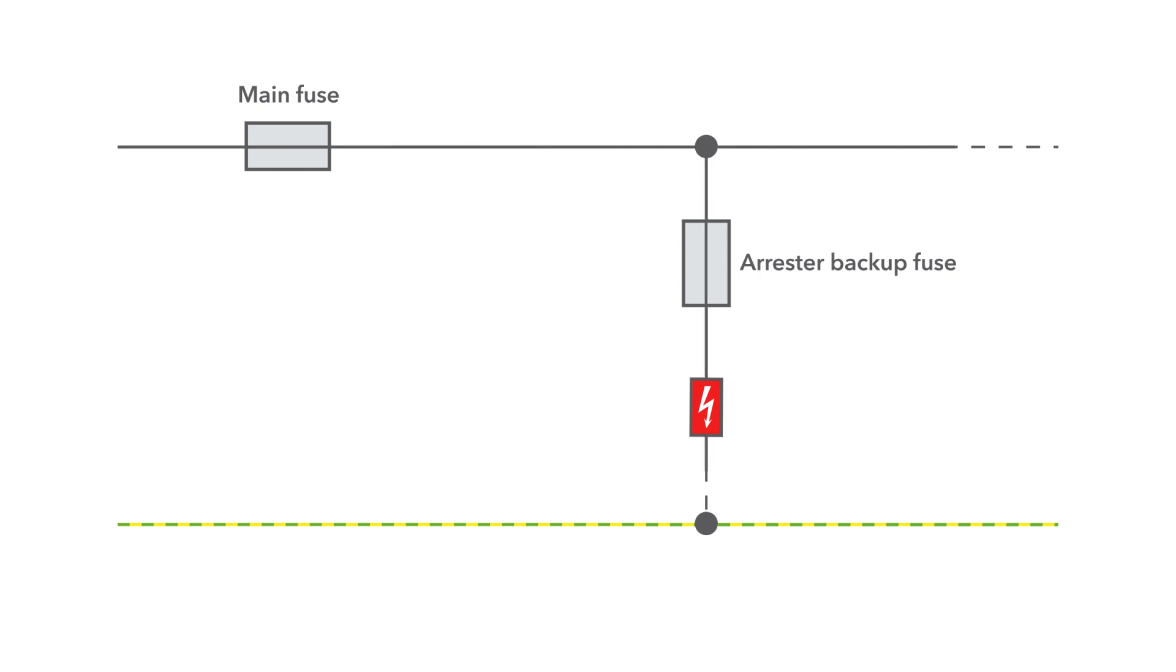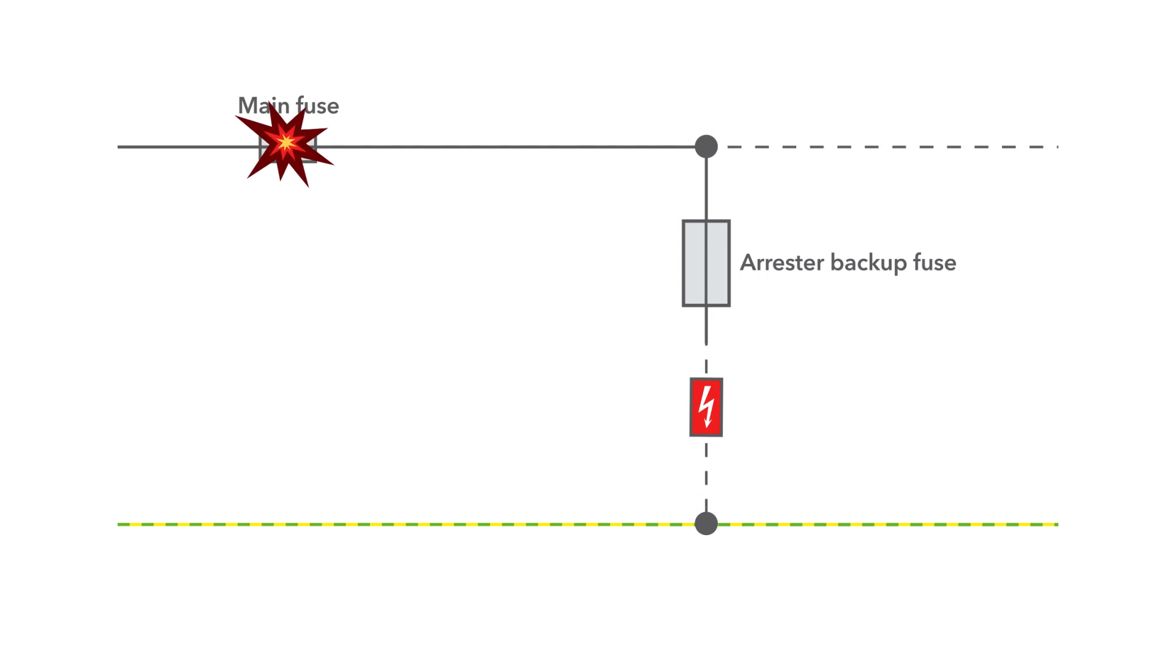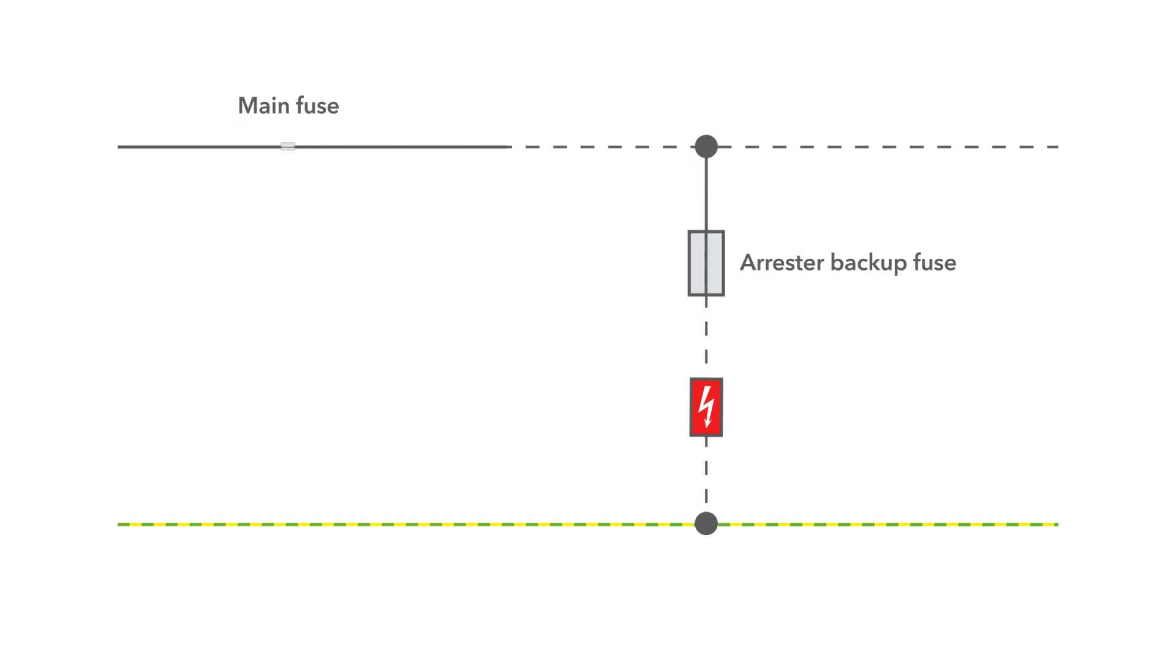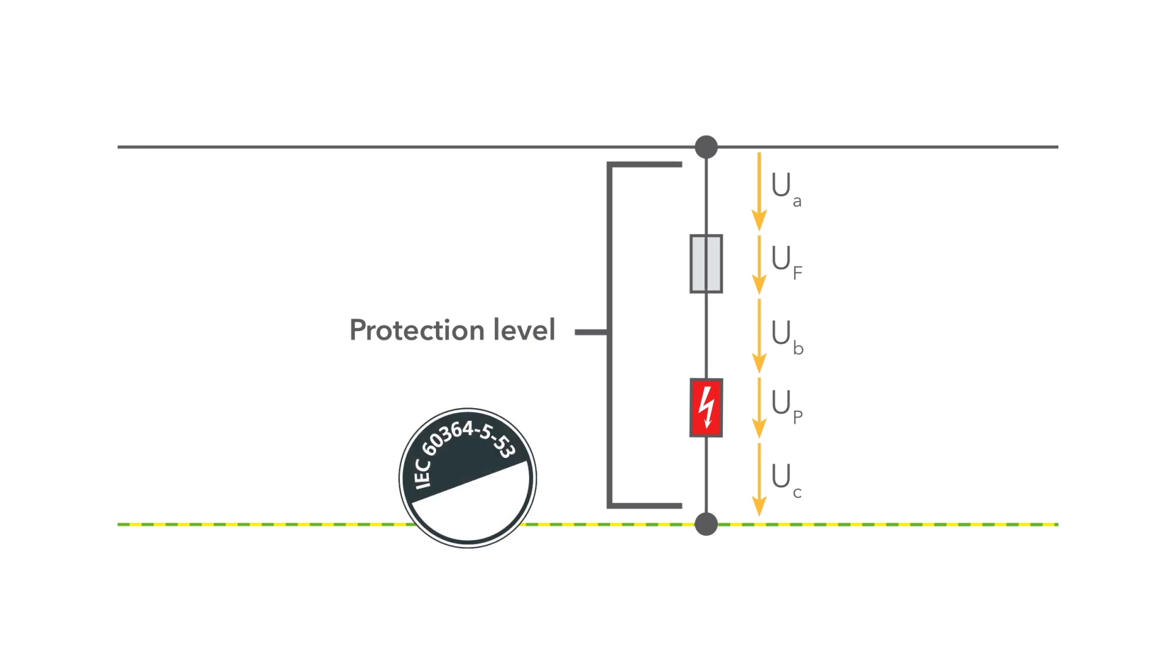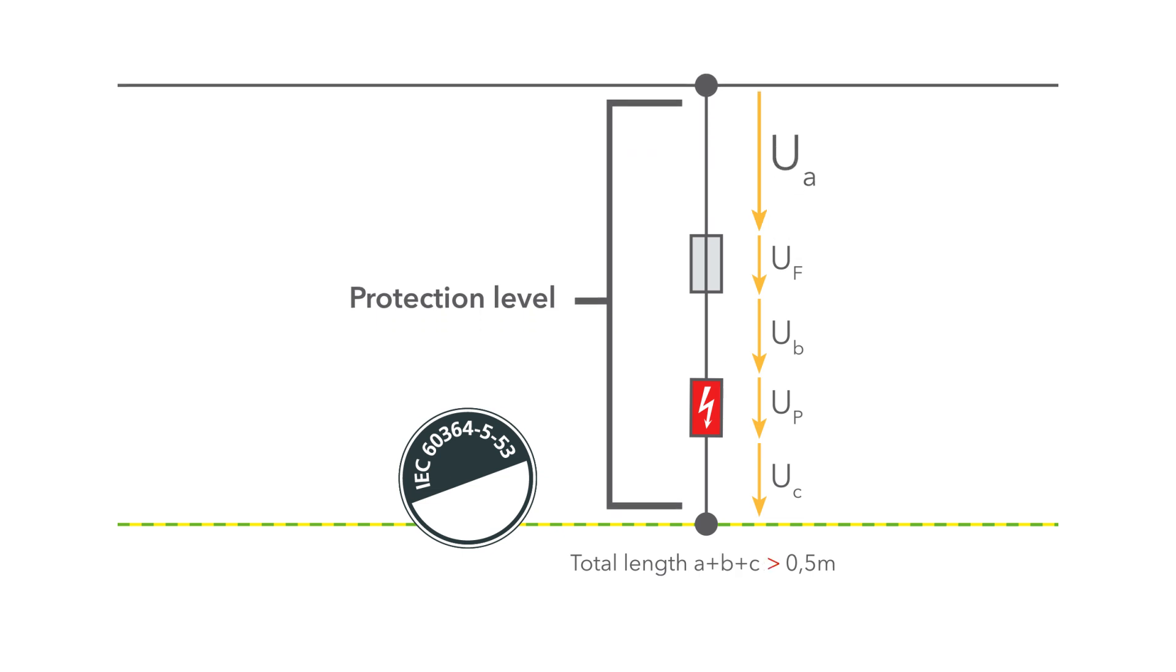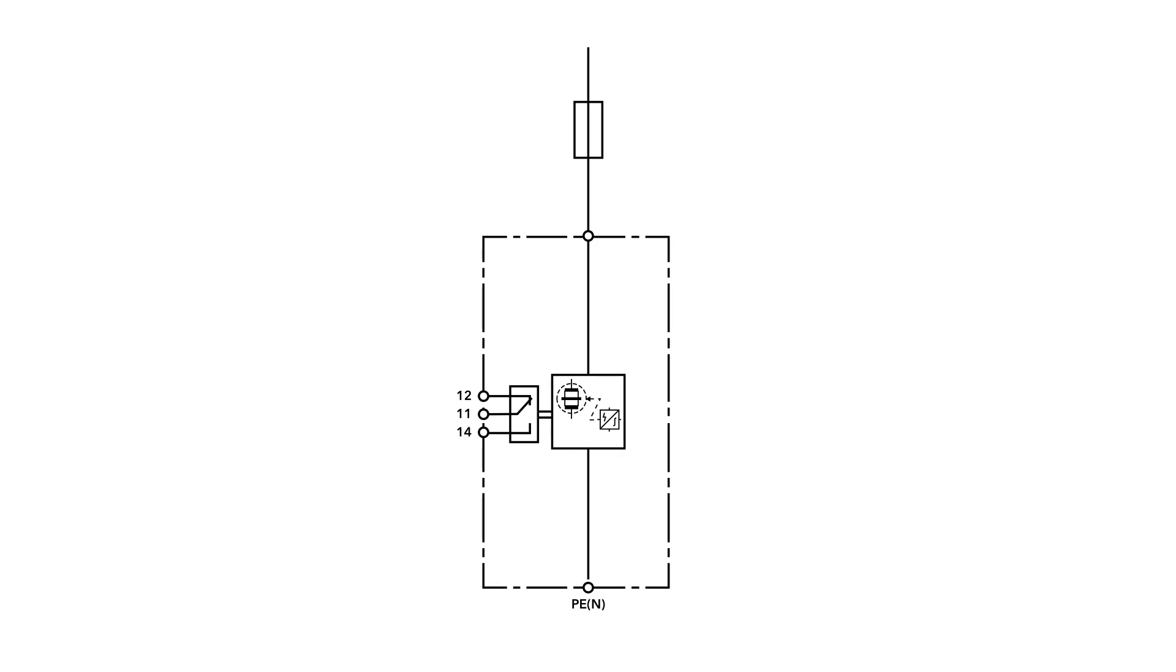In addition, the arrestor backup fuse must be selective to the system fuse. Another problem is the total cable length, which according to IEC 60364 Part 5 Chapter 53 must not exceed 0.5 meters, because a longer cable reduces the protection level. This is difficult to comply with if a backup fuse is used.